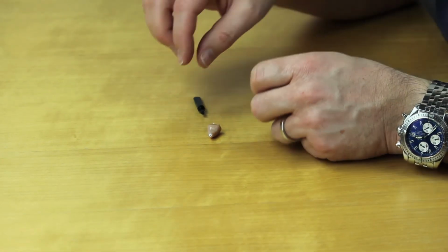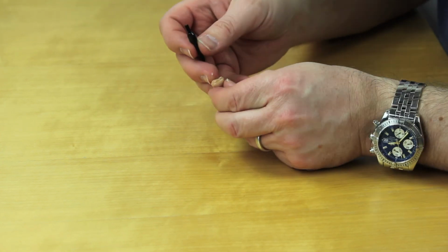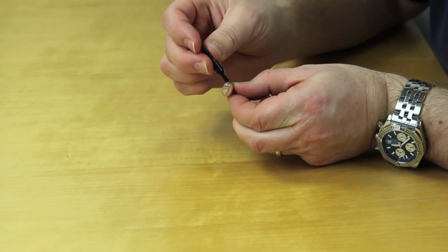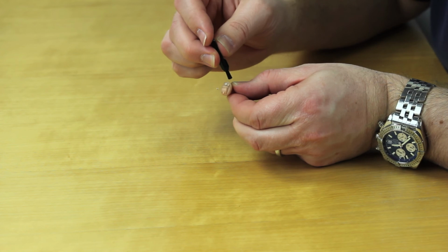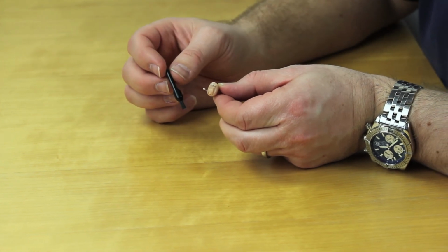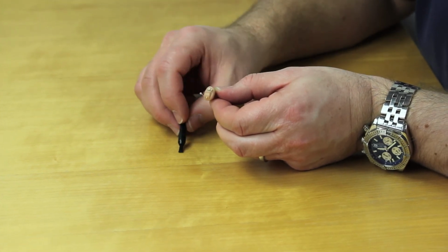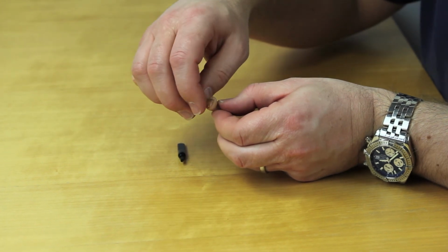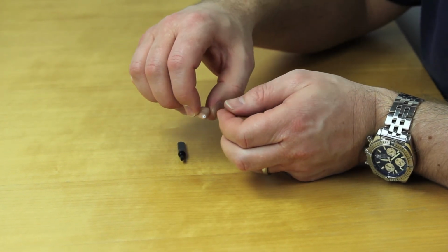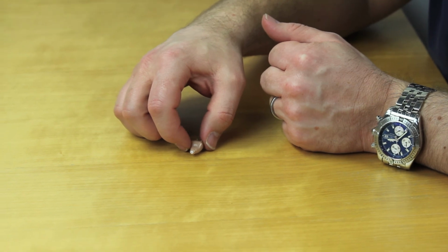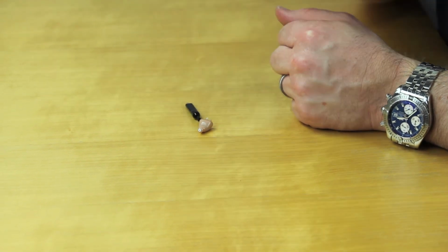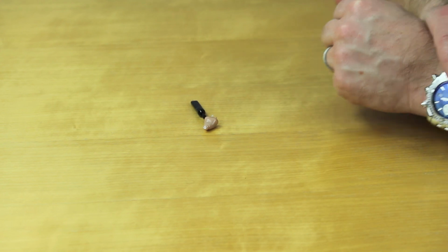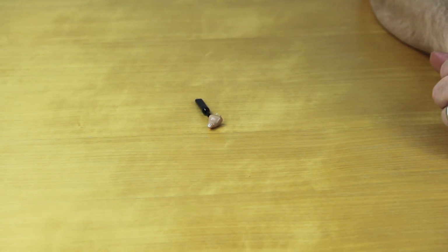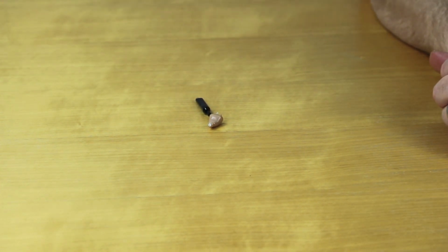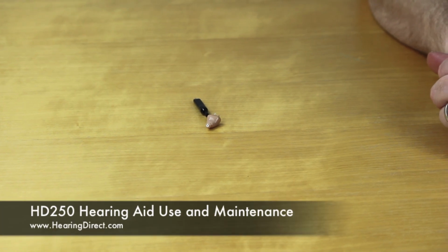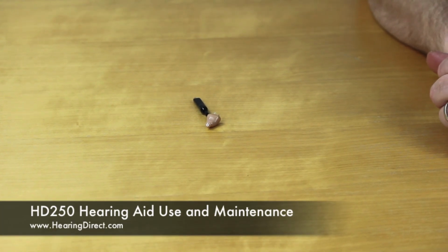The soft brush may also be used to gently brush on and around the microphone opening. If you are using the HD250 with a tip, these will also need to be cleaned and kept free of wax build-up. They may be cleaned using a wipe or medical swab or washing in slightly soapy water. If water is used, please ensure they are left to dry completely before replacing onto the hearing aid. The tips will deteriorate over time and replacements will be needed every 3 to 6 months.